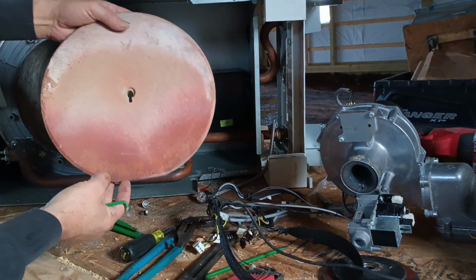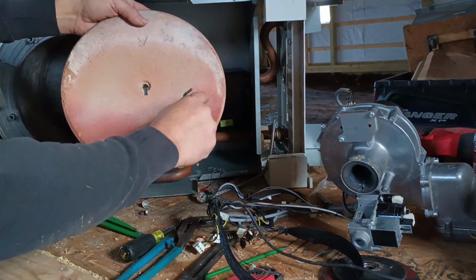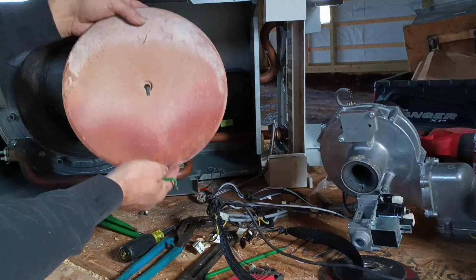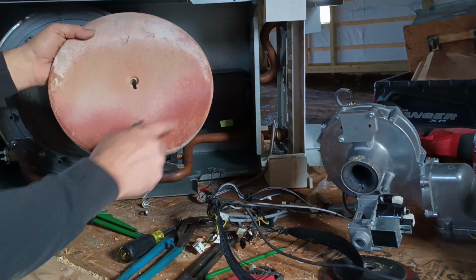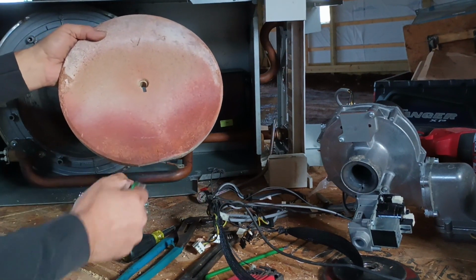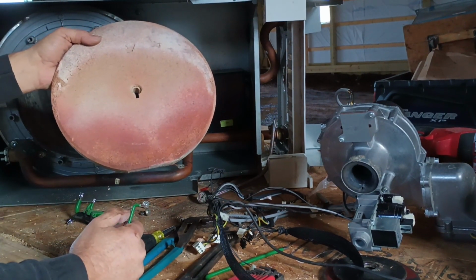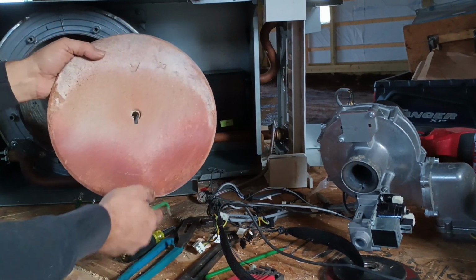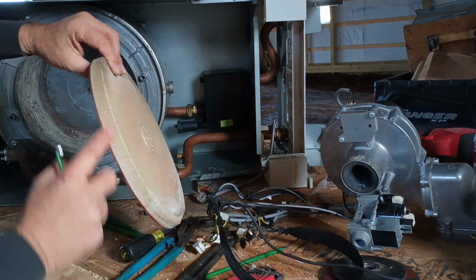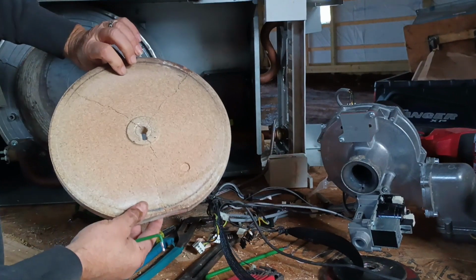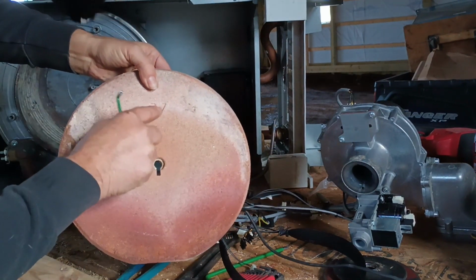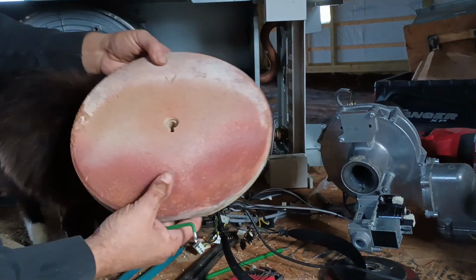The back target wall. Again, this is kind of a telltale sign that we've had a plugged condensate drain, or that we've been holding water in that bottom of the heat exchanger, and that's going to cause the combustion to be off. It's a pretty thick piece of refractory. And of course, Viessmann throws their little V logo in there just because they can.